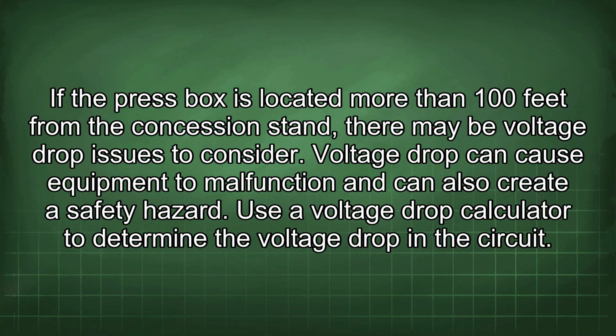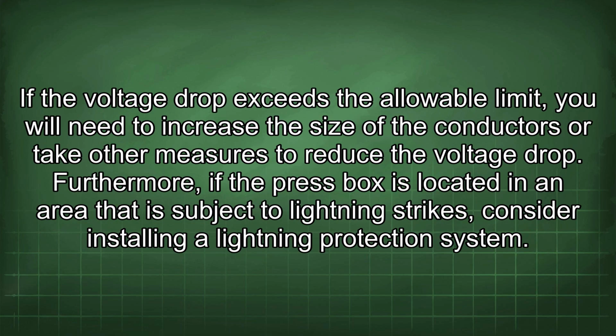If the press box is located more than 100 feet from the concession stand, there may be voltage drop issues to consider. Voltage drop can cause equipment to malfunction and can also create a safety hazard. Use a voltage drop calculator to determine the voltage drop in the circuit. If the voltage drop exceeds the allowable limit, you will need to increase the size of the conductors or take other measures to reduce the voltage drop.